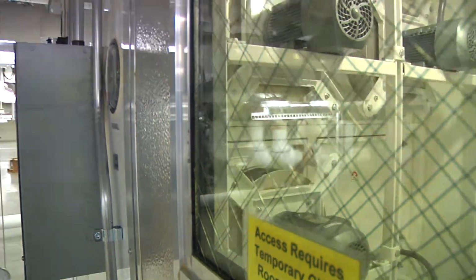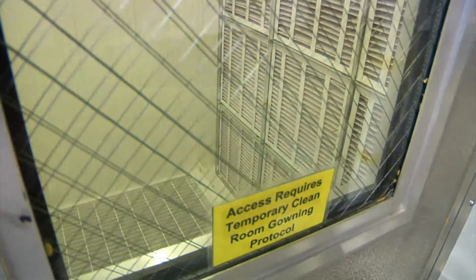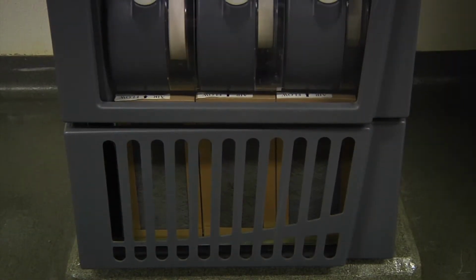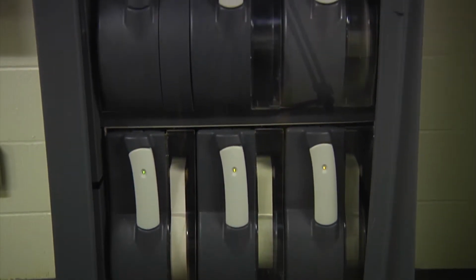About 10% of the air in the clean room comes in through the makeup air system, and 90% of that air is recirculated. We're actually using ULPA filters rather than HEPA filters. ULPA stands for ultra low penetration air filter. A HEPA filter is 99.97% efficient on a 300 nanometer particle. An ULPA filter is 99.999% efficient on a 100 nanometer particle. So a much more efficient filter that's used in this facility to keep the facility so clean.